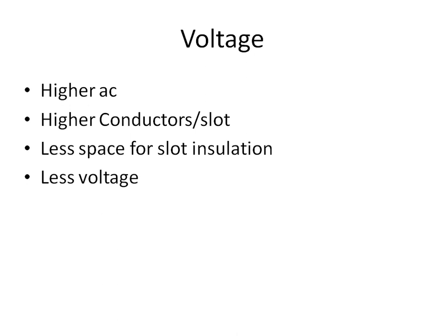And finally, the voltage. We know that ampere conductors is nothing but the number of conductors which will be accommodated in the slot. The slot of stator of three-phase induction motor consists of the conductor along with insulation, because there will be requirement of insulation between the turns as well as between the slot wall and the conductor. So if we have a motor with higher voltage, then the amount of insulation requirement will be more as compared to the requirement of the conductor space.